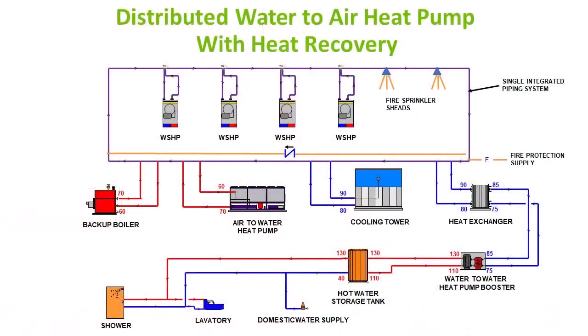Now let's look at heat pumps rather than fan coils. So here's a heat pump, classic boiler tower, right? In here we're going to recover heat. Just inherently, these heat pumps can either add heat into or take heat out of the loop. So if we have some interior zones that need cooling, fine.